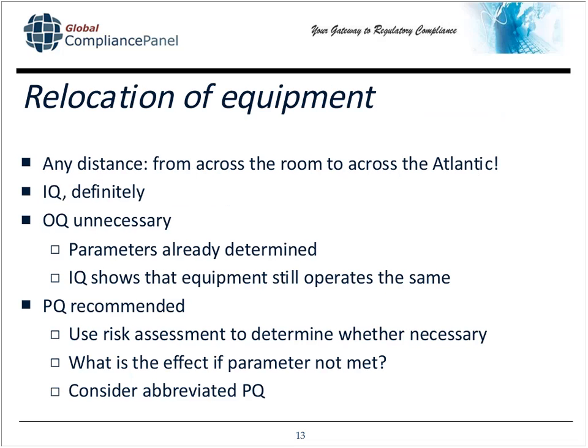So let's say that you have a piece of equipment that you want to relocate. Your manufacturing facility moves, maybe you expand and you move your equipment across the street to a larger building. Even if it's merely across the room, you are taking your piece of equipment and you're moving it. You are rendering your IQ invalid now, because even though you've established your requirements in your IQ, you've got to reperform the IQ itself to establish that the installation is acceptable.